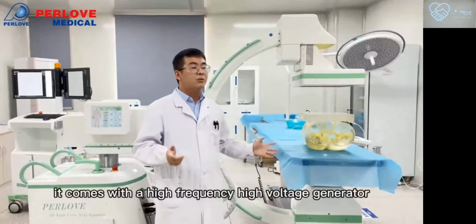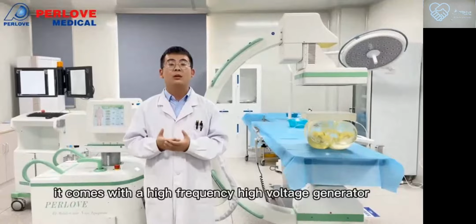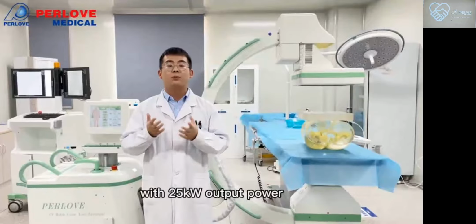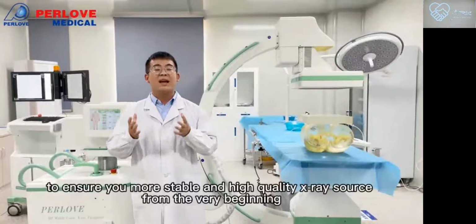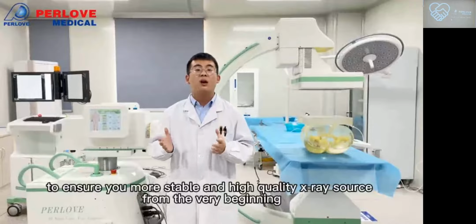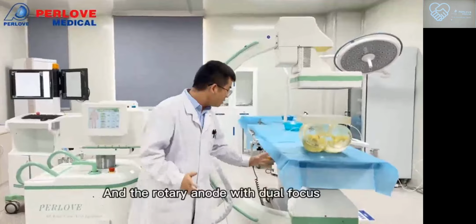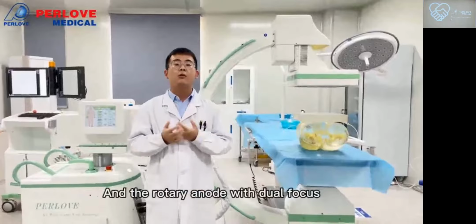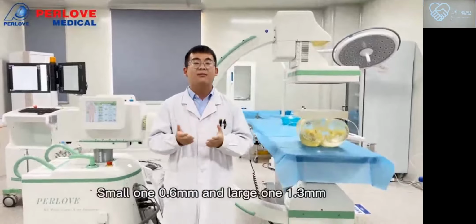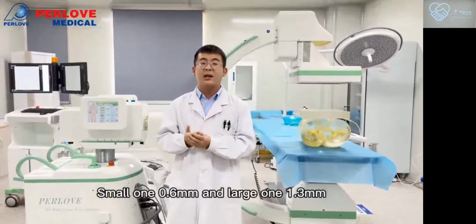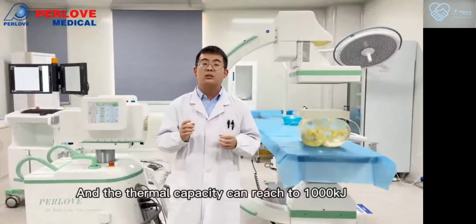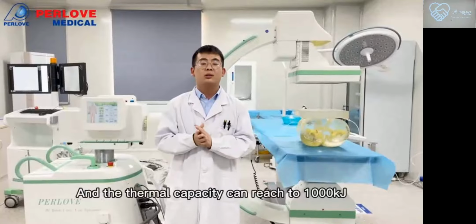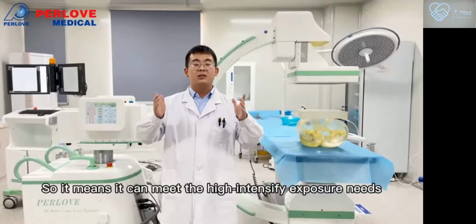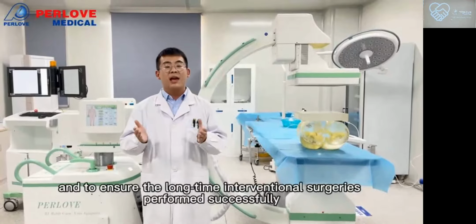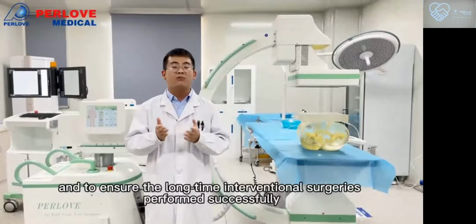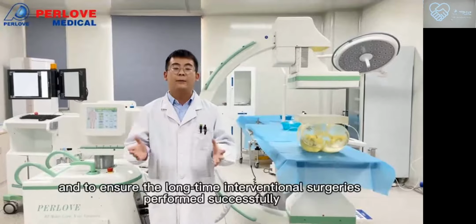This machine comes with a high-frequency, high-voltage generator with 25 kV output power to ensure a more stable and high-quality X-ray source from the very beginning. The rotary anodes have a dual focus, a small one of 0.6 and a large one of 1.3 millimeters. The thermal capacity can reach 1,000 kilojoules. It means it can meet high-intensity exposure needs and ensure long interventional surgeries are performed successfully.